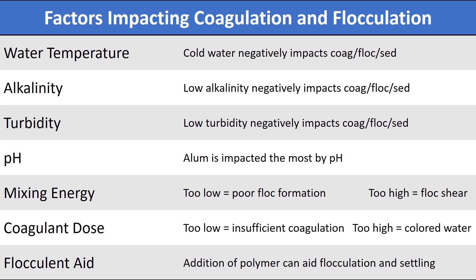An operator must control the mixing energy in each flocculation chamber to get good floc formation without tearing the floc apart. Dose is also important — insufficient coagulant leads to insufficient coagulation, while too high a dose can cause colored water. For example, too much alum will cause bluish or milky colored water in the distribution system, whereas too much ferric or iron-based coagulant can cause yellow water delivered to customers. The addition of polyelectrolytes or polymers — flocculant aid — will improve the coagulation and flocculation process.